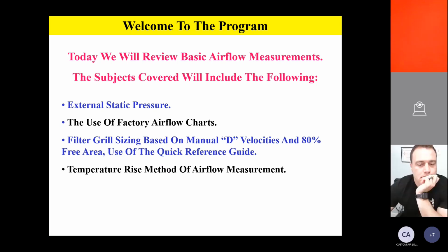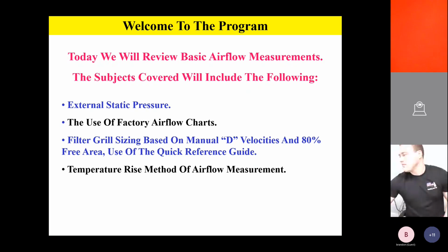In addition, we're going to talk about filter grill sizing based on manual D velocities. Now remember, guys, manual D is kind of the Bible, if you will, for residential duct design. So we're going to dig into some filter grill sizing, and I've produced a little quick sheet. That quick sheet is actually based on manual D recommended velocities across the filter grill, a return grill, and 80% free area. So let me stress that one more time.